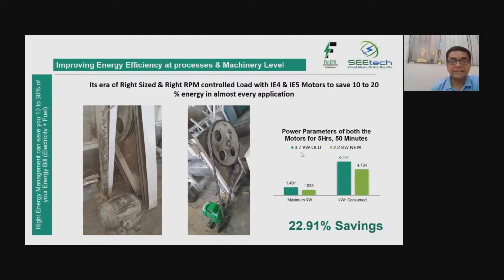So the scope for saving came from three sides: the motor was oversized, it was continuously rewound multiple times, and it was fundamentally of lower efficiency. So there were three pointers for us to work on this particular motor. When we replaced it with a 2.2 kilowatt motor, the results are in front of you.